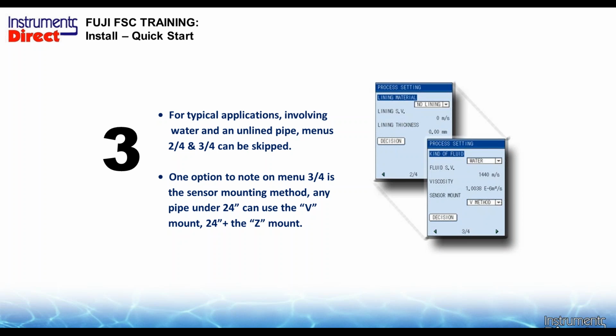Also, we need to note there that we almost skipped on 3.4, you need to select the type of process liquid. 95% of you will use water. Even if you have some mixtures there, a rule of thumb is plus or minus 10% of the sound speed, don't worry about it. The flow meter will optimize performance. If you look on the diagnostic screen, you'll see the sound speed changes all the time there. Kind of the autopilot function of the state of this technology, not so much with some of the older devices there.